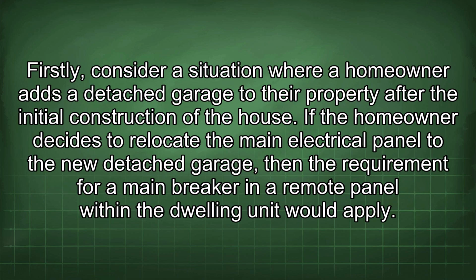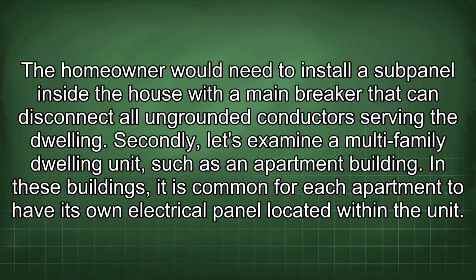Firstly, consider a situation where a homeowner adds a detached garage to their property after the initial construction of the house. If the homeowner decides to relocate the main electrical panel to the new detached garage, then the requirement for a main breaker in a remote panel within the dwelling unit would apply. The homeowner would need to install a subpanel inside the house with a main breaker that can disconnect all ungrounded conductors serving the dwelling. Secondly, let's examine a multi-family dwelling unit, such as an apartment building.